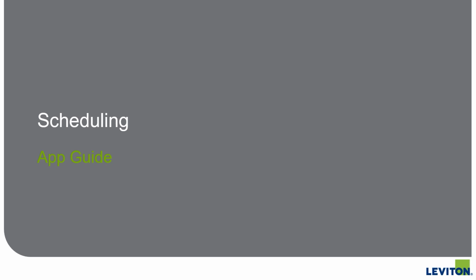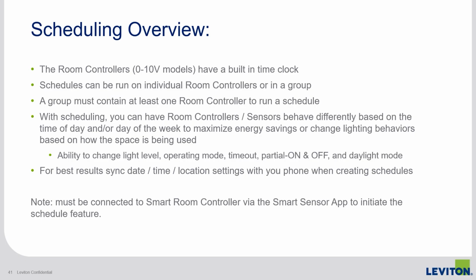Here you can create behaviors and have them run at set times during the day and week. The room controller models are 0 to 10 volt dimming models with built-in time clocks. Schedules can be run on individual room controllers or in a group that contains at least one room controller. With scheduling, room controllers and sensors behave differently based on the time of day and/or the day of week to maximize energy savings or change lighting behaviors based on how the space is being used.